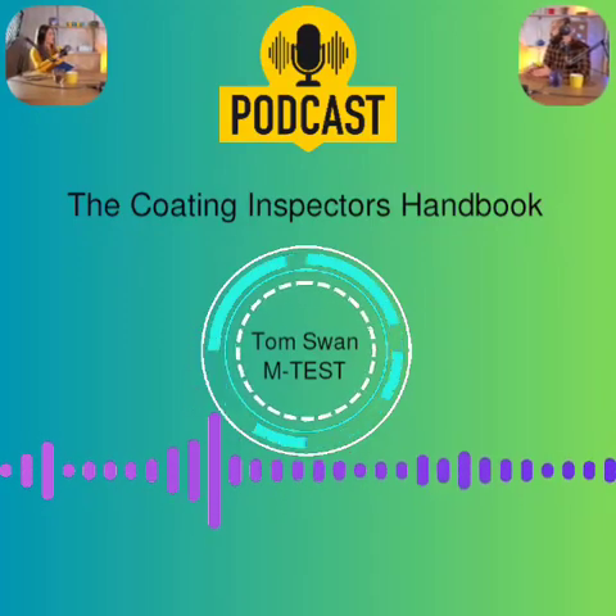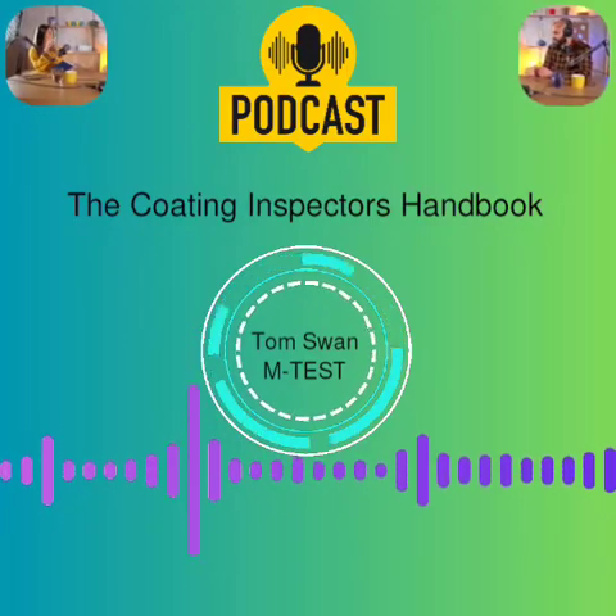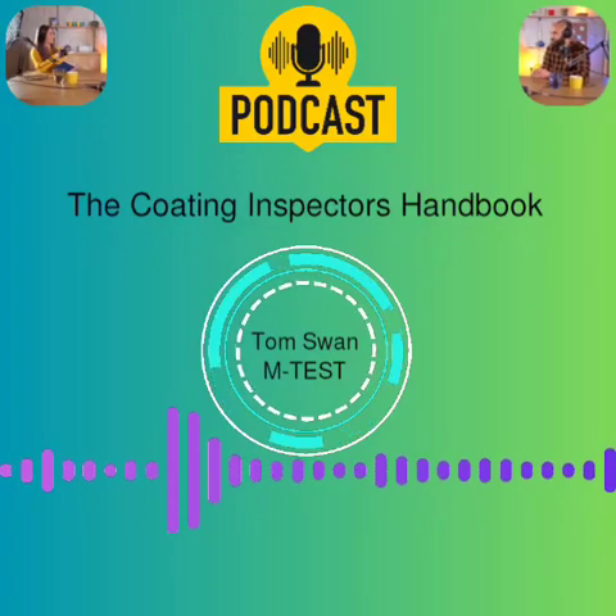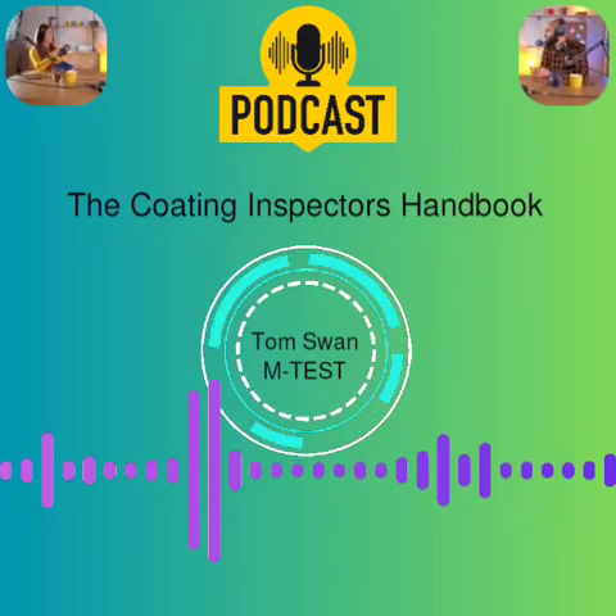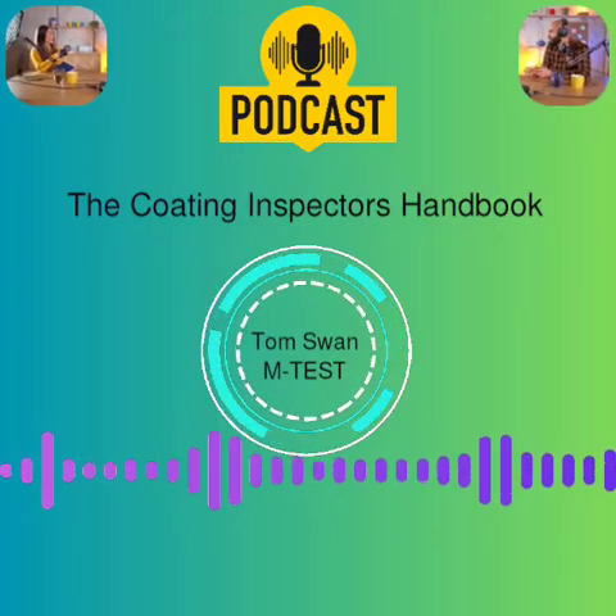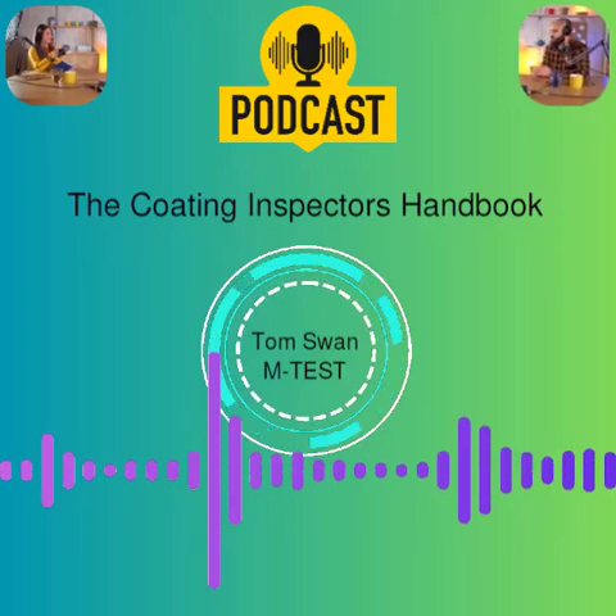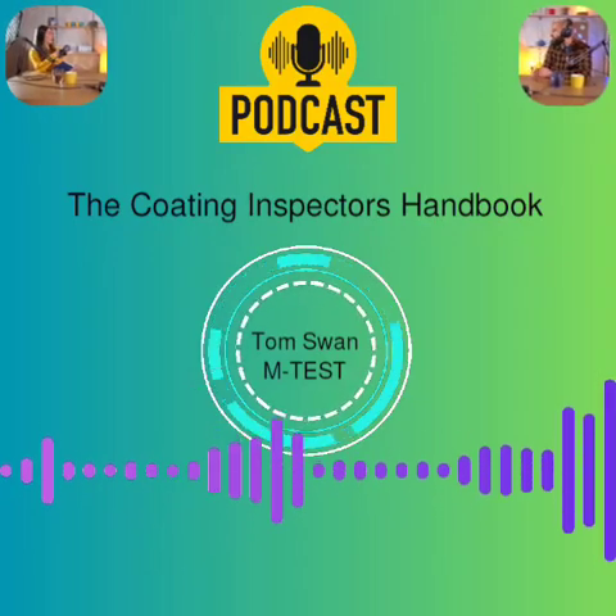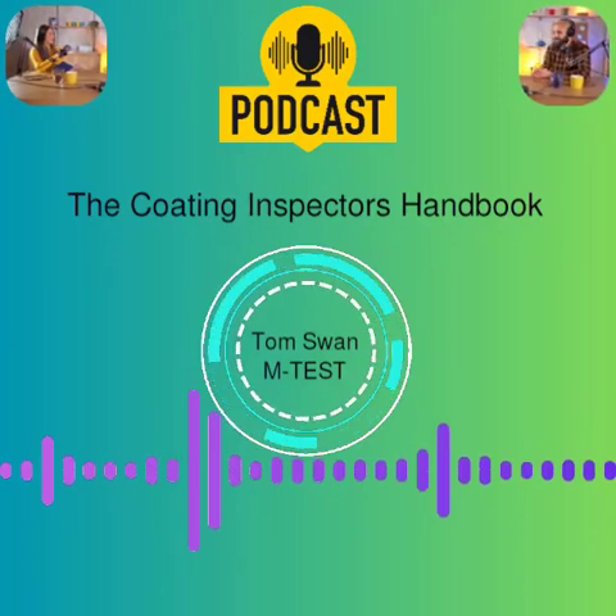Storage matters too. Yeah, keep it in the shade. Don't let the instrument itself heat up. Check the wick on the wet bulb, needs to be clean, white, flexible. Dirty wicks mess up evaporation. Use distilled water if you can. And make sure that wick is properly soaked. Water shouldn't bead up on it.